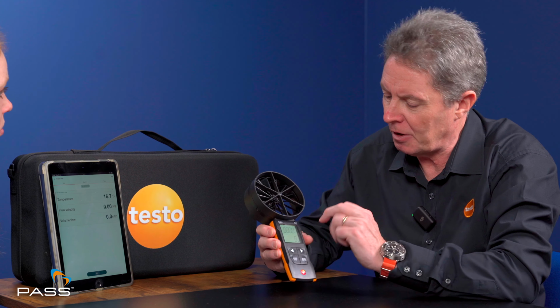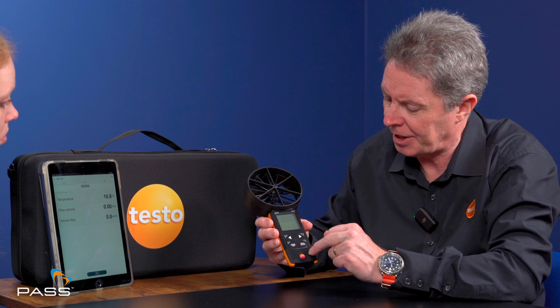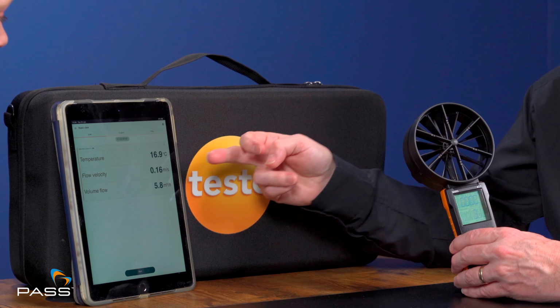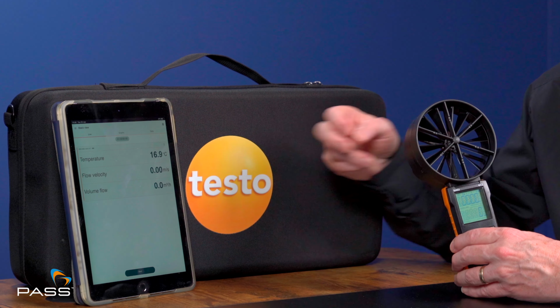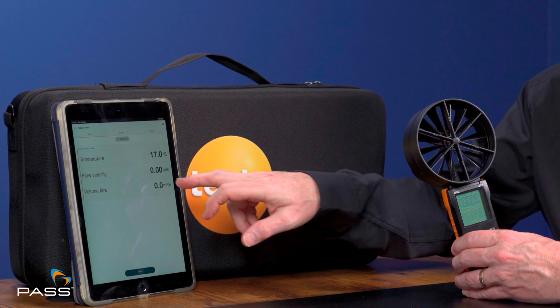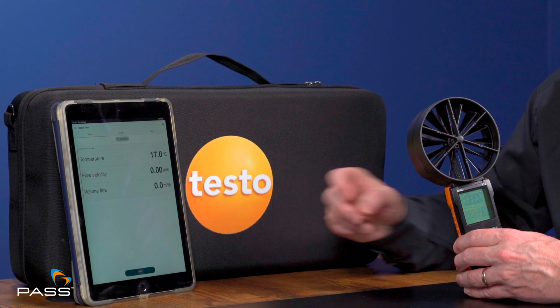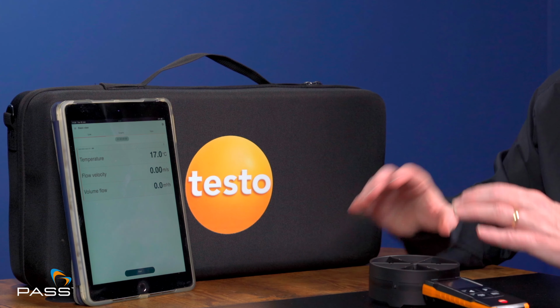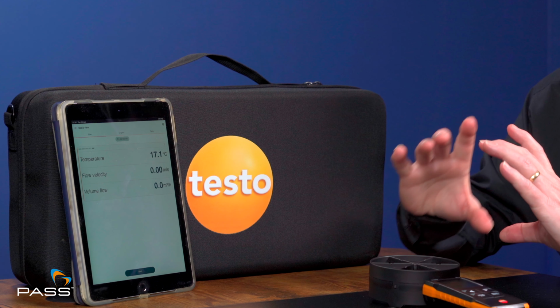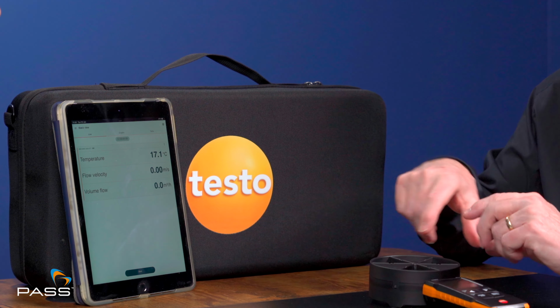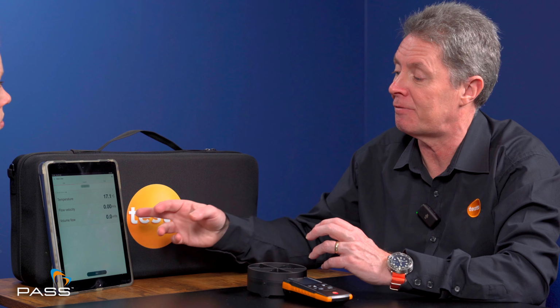And what we have on here, you obviously have a display, but also this is connected via Bluetooth to our Testo Smart app. And what we can see here, typically, is the airflow temperature and the flow velocity, in other words, the speed of the airflow through here. And also, within the app, we input the actual geometry of the size of the duct. Because we've got the flow velocity and we've told it the duct area size, it will calculate the flow volume.